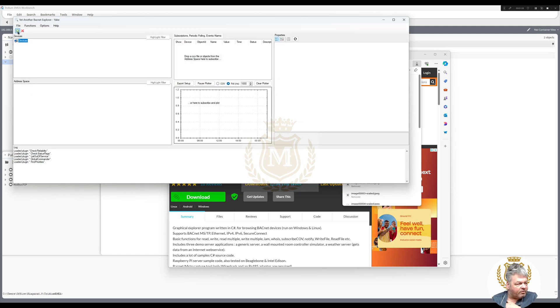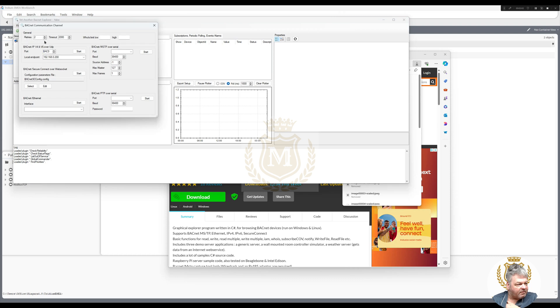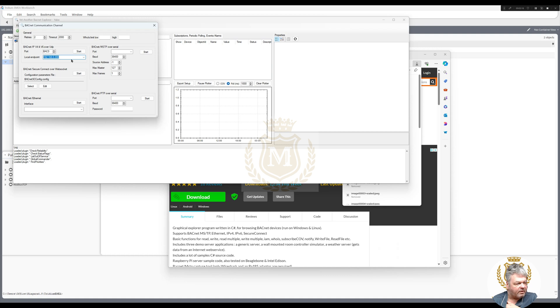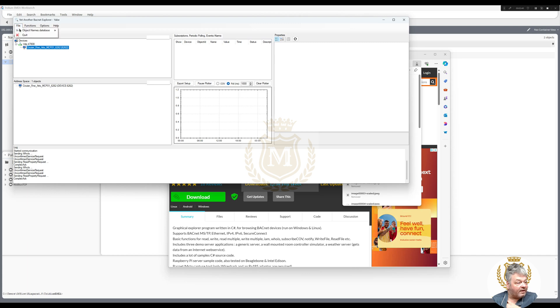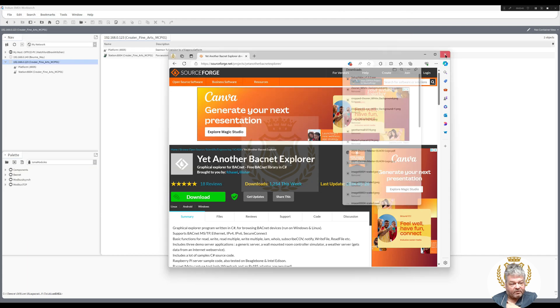We'll just add another device. Go to Add Device. I know that my local endpoint — this PC — is on 192.168.0.200, and the MAC 36 is on .1, .2, .3 at the end. Start that. It's picked up the MAC 36 with the 6262 device. It hasn't picked up any points — there are no points there. That's expected. Let's close that down for now — we don't need that anymore.